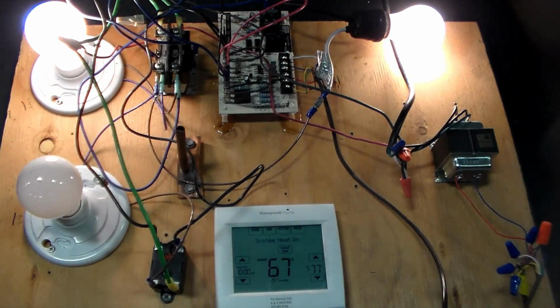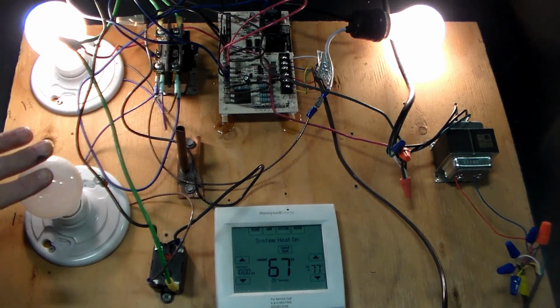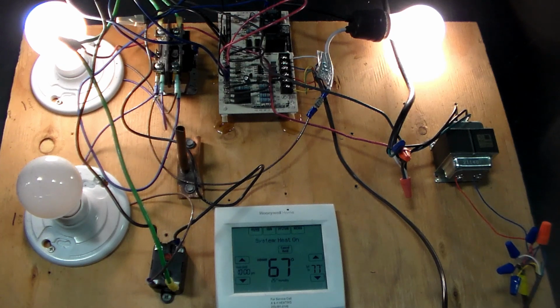Since I have my defrost timer or my defrost sensor jumped out, the board thinks that it needs the defrost. So we could wait here for 30 minutes to go by, or I could just hit the test button and we can see what happens. Right now, imagine that we're burning away in heat mode. We've got our compressor on, our condenser fan is on, but my reversing valve is not on because I'm failing to heat mode. Reversing valve is not energized.